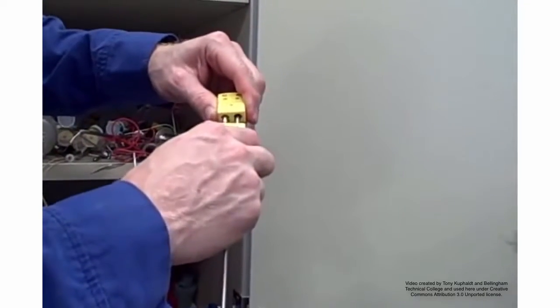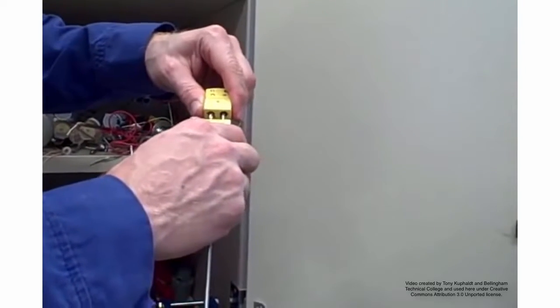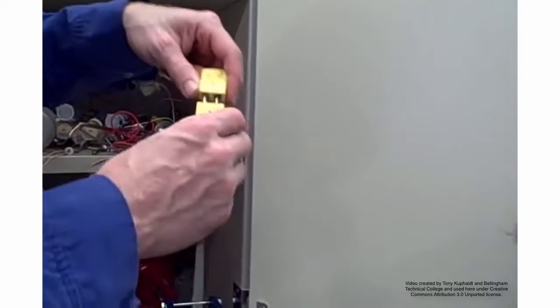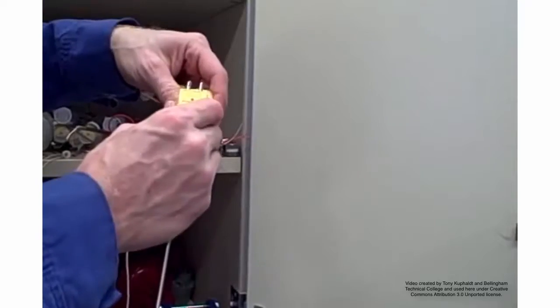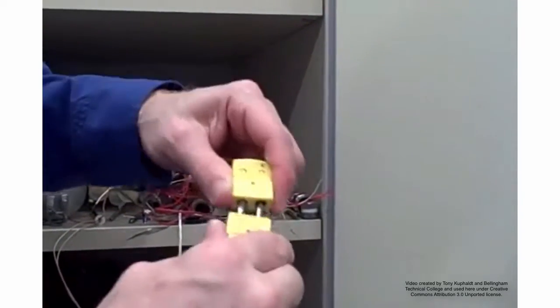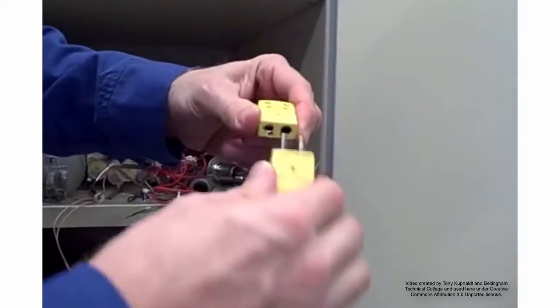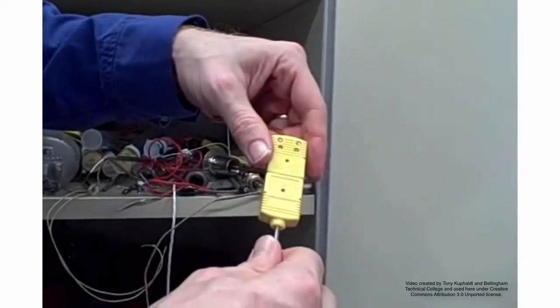However, never underestimate some people's ability to force connectors where they shouldn't go. I've seen thermocouple connectors shoved backwards like this. You really got to wonder about the person, but they put a lot of force in here, and they actually managed to get it in. It's supposed to go in like this, a polarized plug.